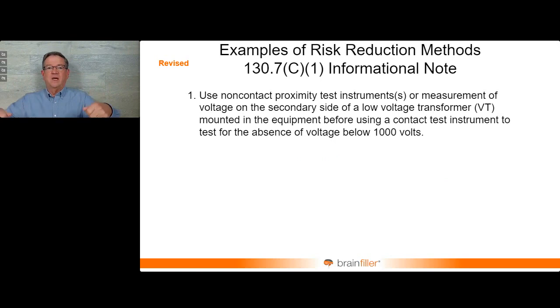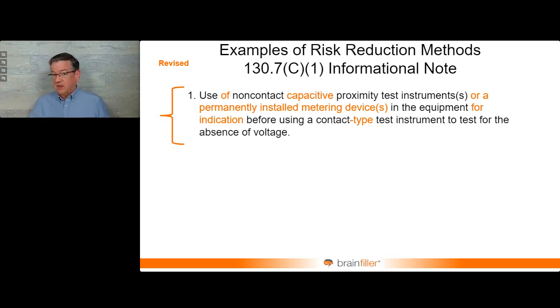Before you go in and do contact voltage testing. So this was the original language, which was changed for 2024, where what you do is basically use a capacitive proximity tester. So you're getting in proximity to basically buzz the line to see if there's a voltage. Now be careful, because these don't technically tell you absence of voltage, they tell you presence of voltage. So there could still be a little bit of voltage. So it doesn't mean that it's dead until you've used a contact device.